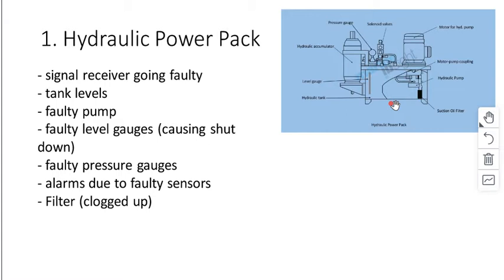We've got faulty pressure gauges as well, and so on. They may show zero or go too high, and with safety features, they might take the system down. And then we may have false alarms due to faulty sensors as well in the hydraulic power pack. And then obviously we've got a filter as well in the power pack, very, very important.